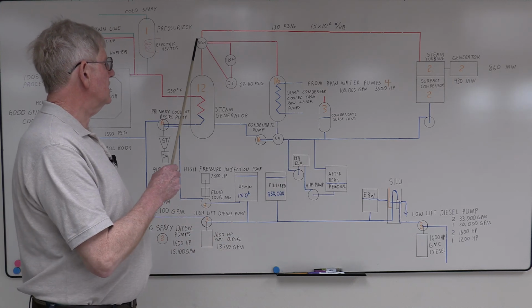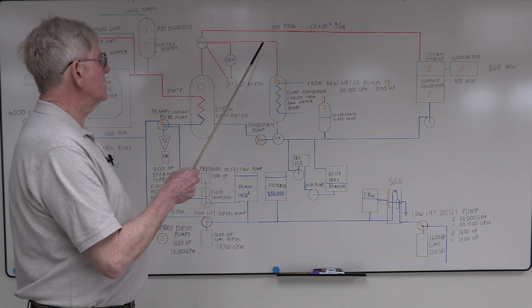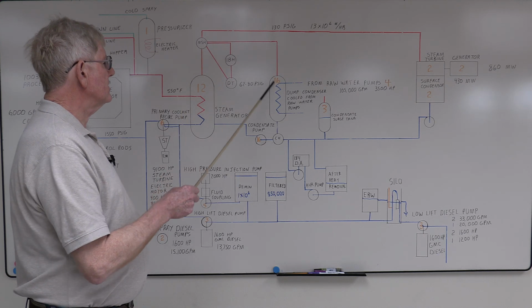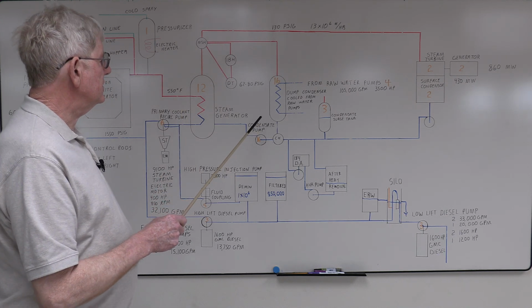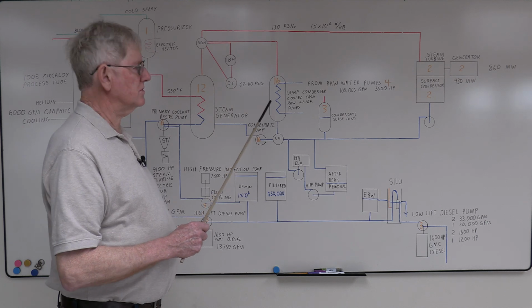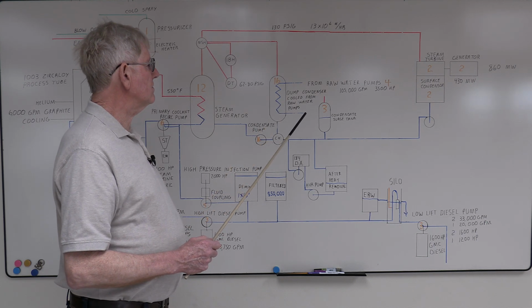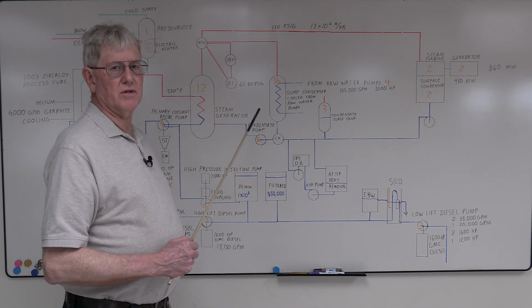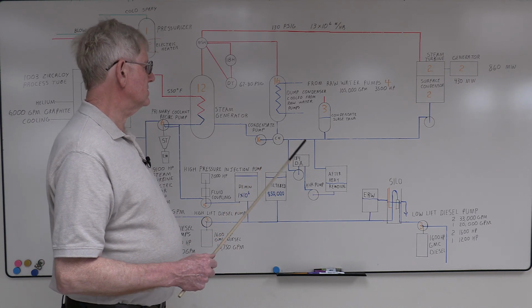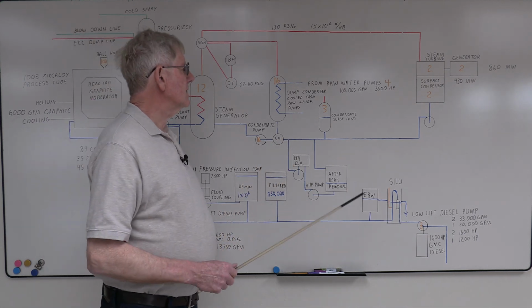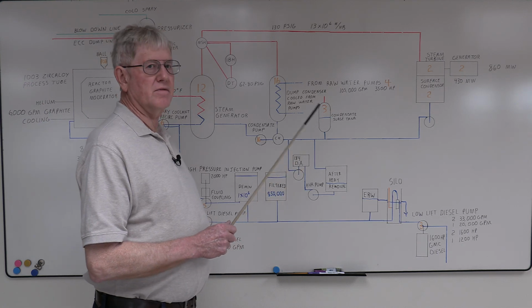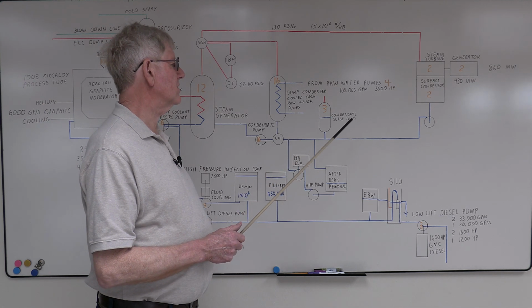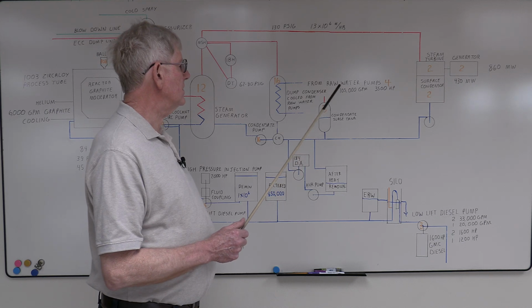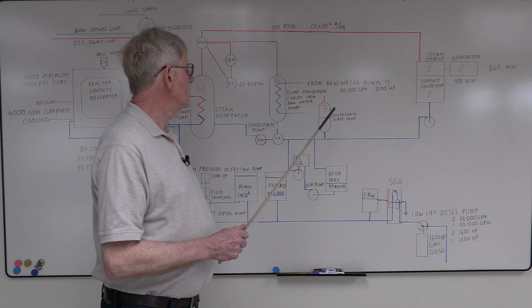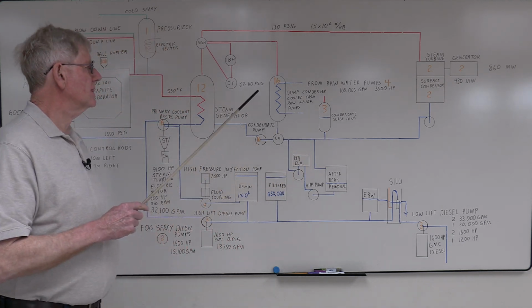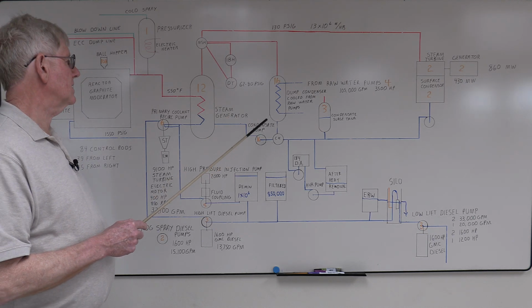If the pressure got too high in the main steam header, it's set for about 130, it went through the dump condensers. These were used for startup and shutdown also. They got raw water from the river. This plant called all the water coming in raw water because there's various treated water. There's 4 pumps. They rate 105,000 gallons a minute, about 3,500 horsepower synchronous motors, help balance the plant power factor. Usually they'd have 4 of these dump condensers warmed up and running in case of a reactor scram.